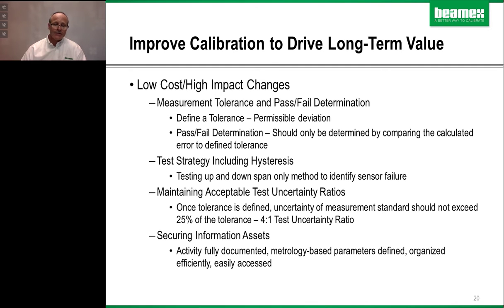As these programs evolve, it is relegated to a technician's gut feel. They've been doing it a long time, and they say, well, is it within tolerance or not? The problem that presents is that it is recorded in perpetuity as a passing calibration when in fact it really wasn't mathematically calculated, and it can present problems. The operators are making decisions based on this measurement. So assign a tolerance and then actually calculate what that error is so we can compare it to the tolerance.